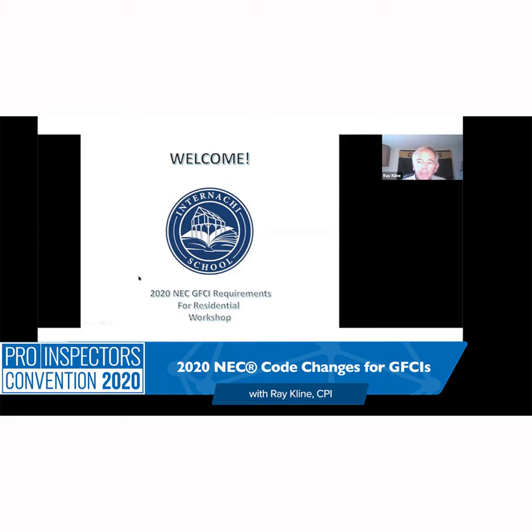So when they talk about 250 volt circuits now, what they mean is we're going to have to look for GFCI protection on dryers, ranges, exterior ACs, you know, any place where you might be within 6 feet of a water source or potentially wet ground.